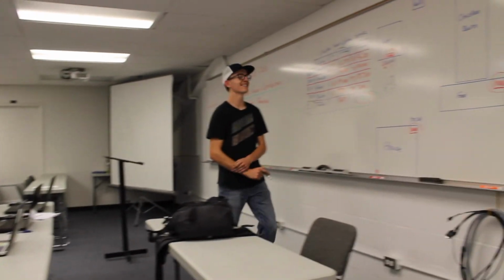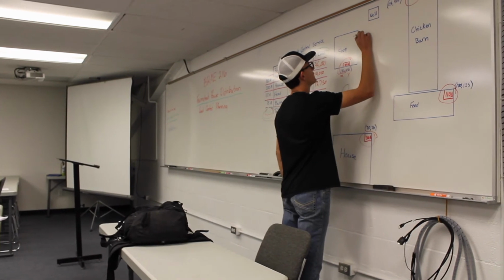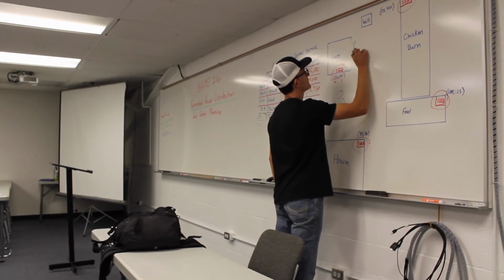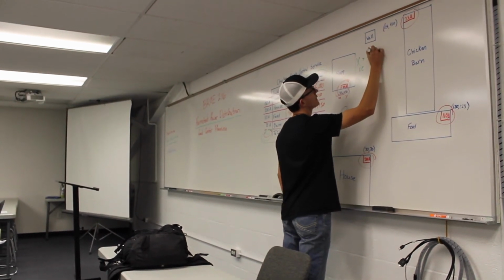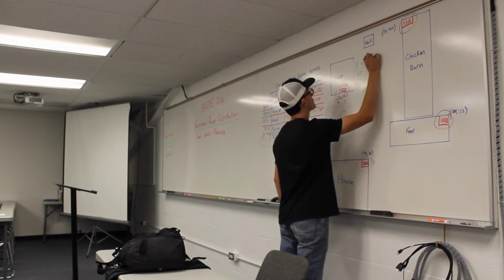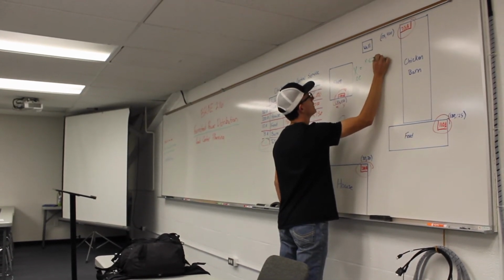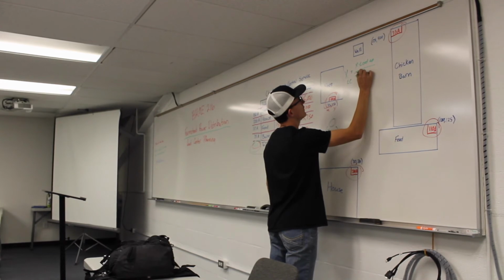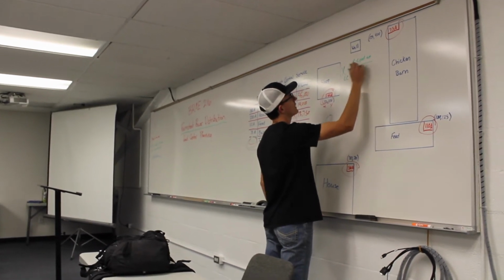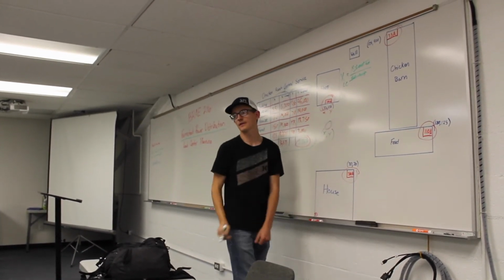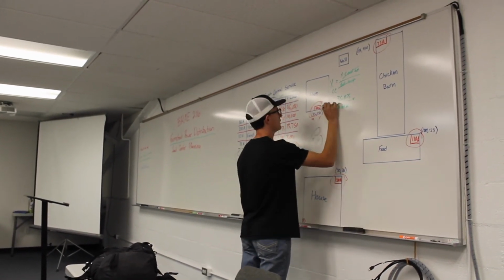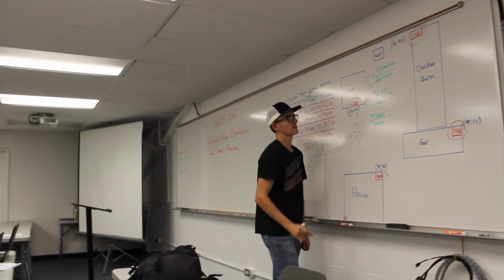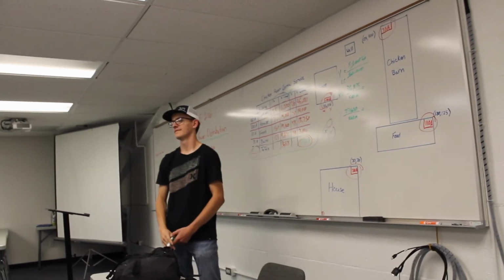That's close, but you're off by a little bit. Shoot. So for the x coordinate of the load center, it'll be equal to the weighted x coordinate of each building summed, so x load total, over the total load. So with some canceling out, you end up with just an x value for your x load center. So for ours, it will be 30. Somebody give me answers for both of those. The x value is going to be 65.3.